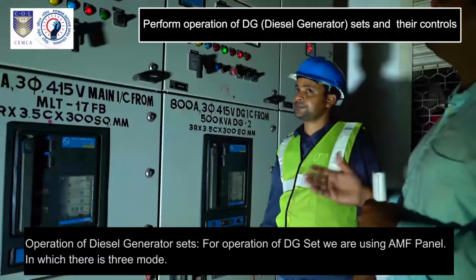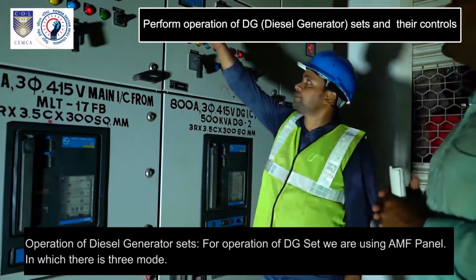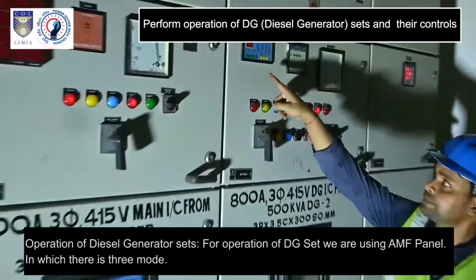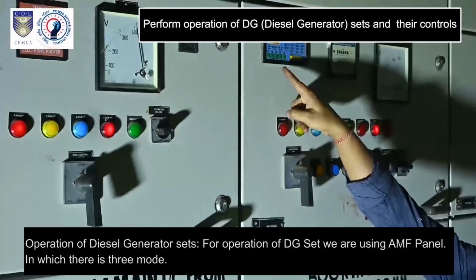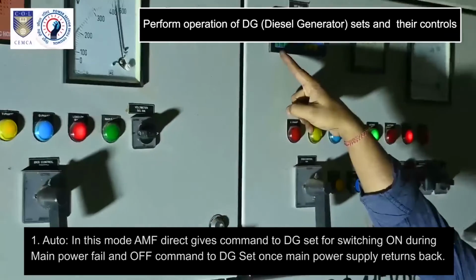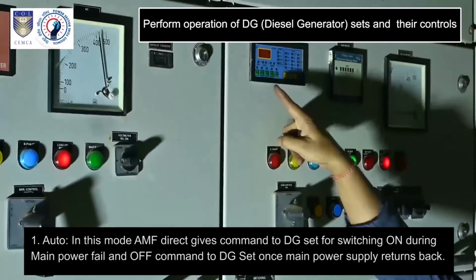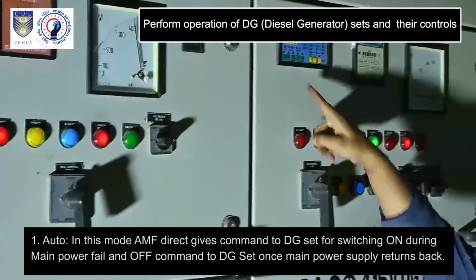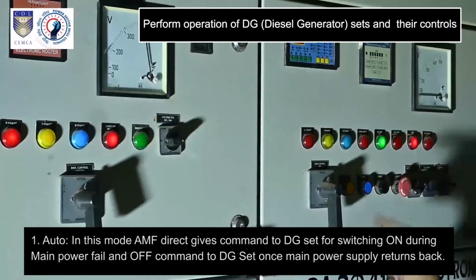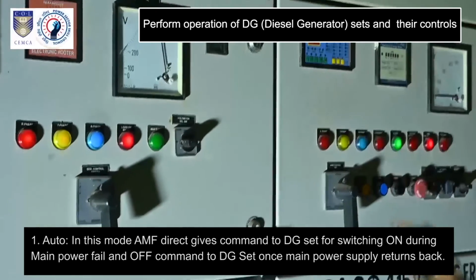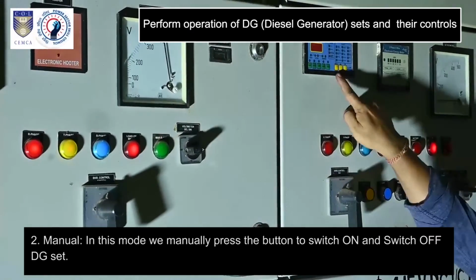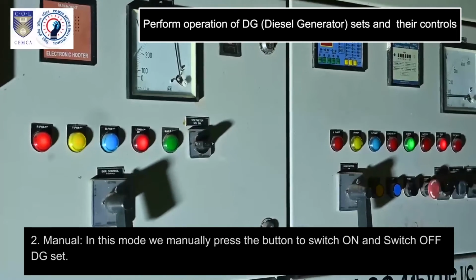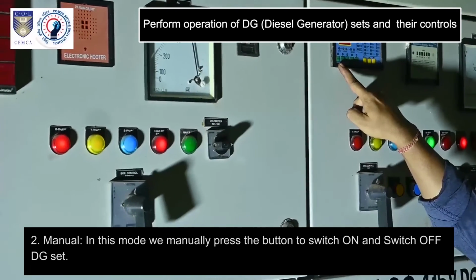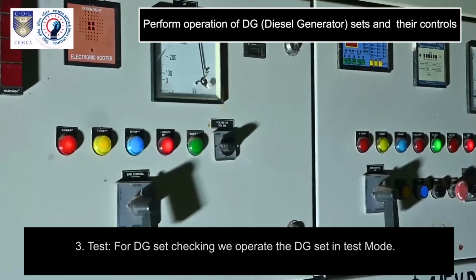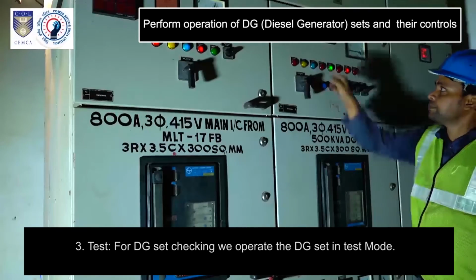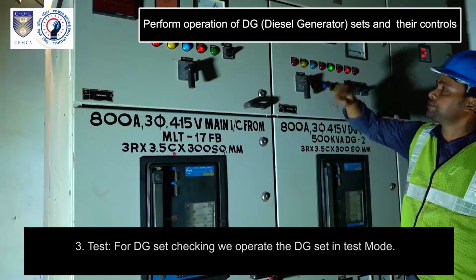Operation of diesel generator sets. For operation of the DG set, we are using an AMF Panel, in which there are 3 modes. 1. Auto. In this mode, the AMF directly gives a command to the DG set for switching on during main power failure, and an off command to the DG set once the main power supply returns. 2. Manual. In this mode, we manually press the button to switch the DG set on and off. 3. Test. For DG set checking, we operate the DG set in test mode.